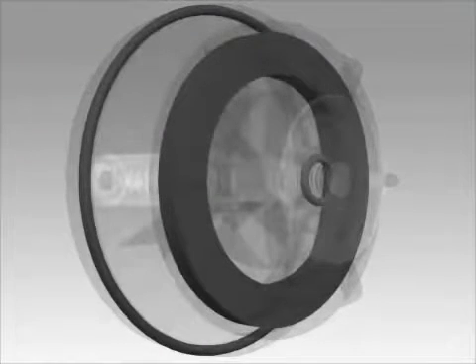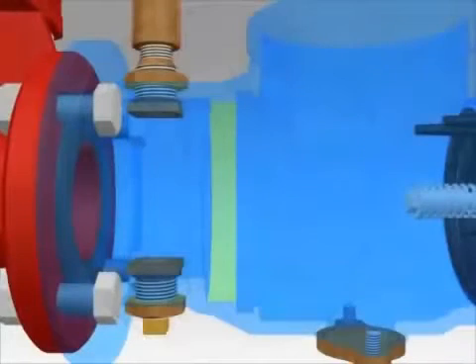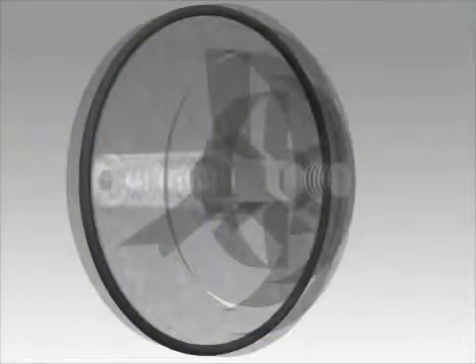If you are installing a repair kit, replace the seal ring, seat O-ring, and stem O-ring. Reassemble the check and tighten the retainer nut. Clean and inspect the O-ring sealing area in the body. Next, lubricate the seat O-ring.